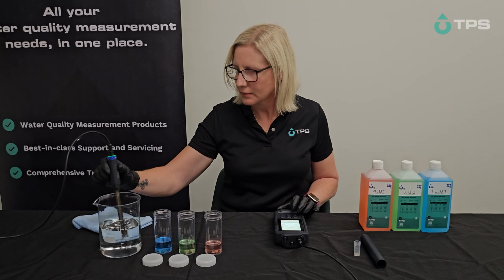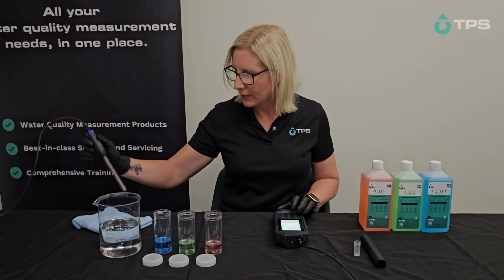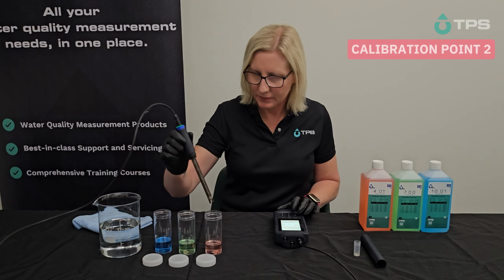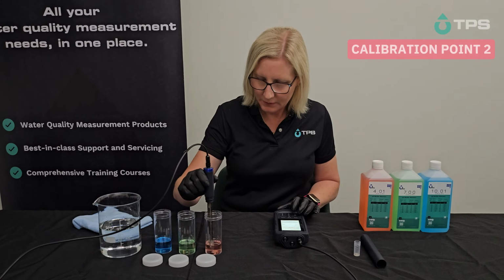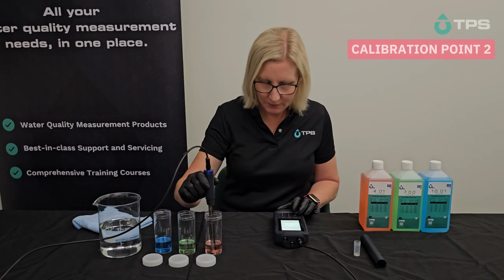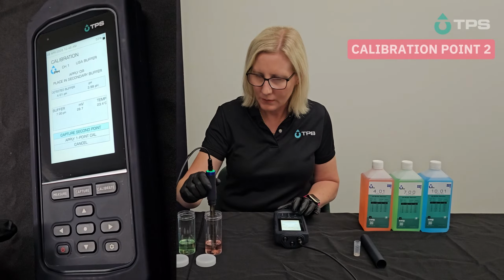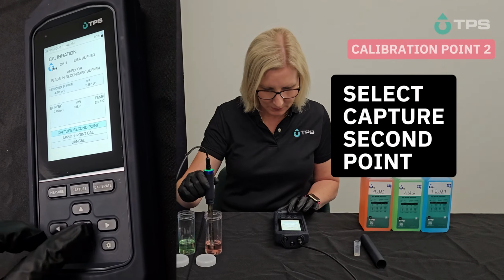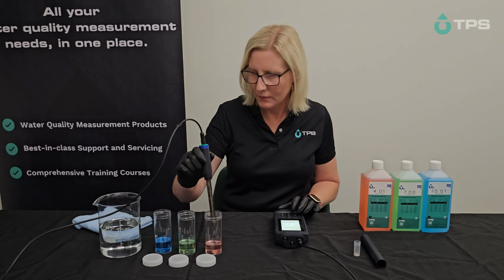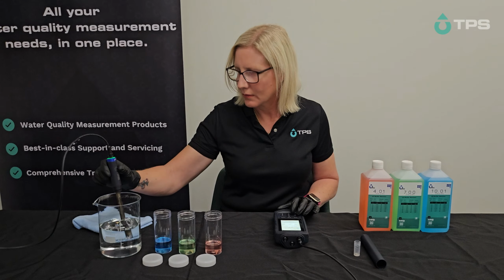Remove from the primary buffer and rinse the sensor tip with deionized water. Immerse the sensor tip into your secondary buffer sample jar. Gently stir and wait for stabilization. Once the reading is stable, select Capture Second Point. Rinse the sensor tip with deionized water.